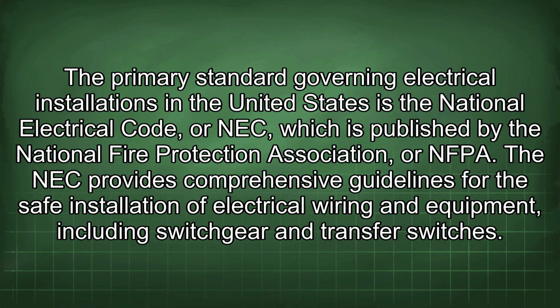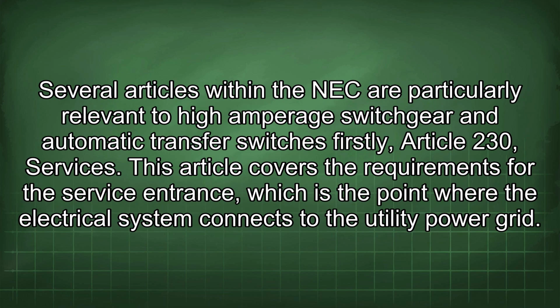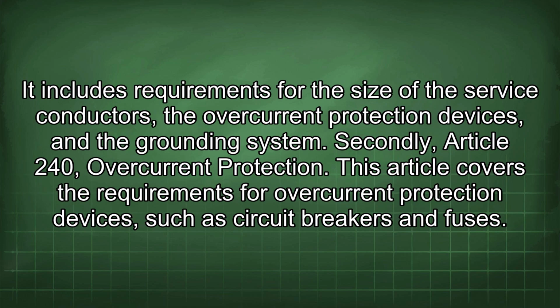The NEC provides comprehensive guidelines for the safe installation of electrical wiring and equipment, including switchgear and transfer switches. Several articles within the NEC are particularly relevant to high amperage switchgear and automatic transfer switches. Firstly, Article 230, Services. This article covers the requirements for the service entrance, which is the point where the electrical system connects to the utility power grid. It includes requirements for the size of the service conductors, the overcurrent protection devices, and the grounding system.